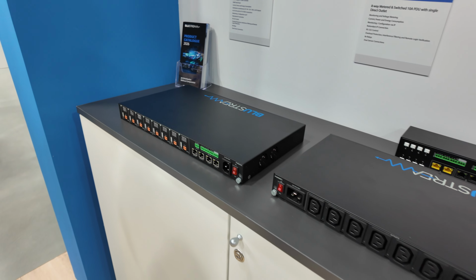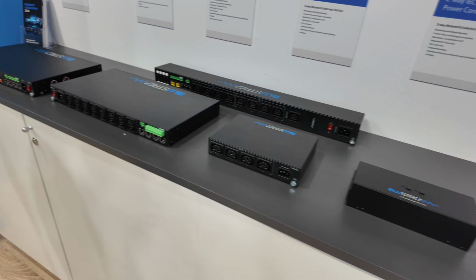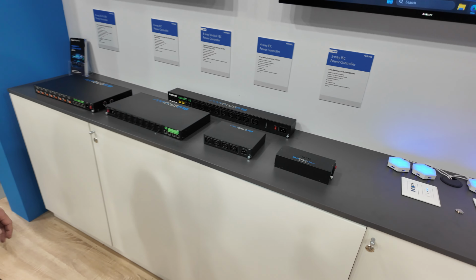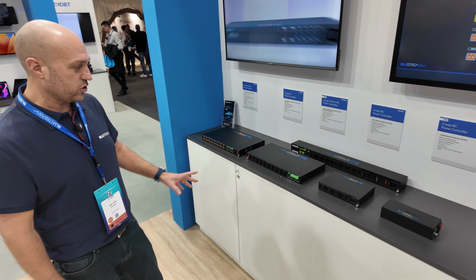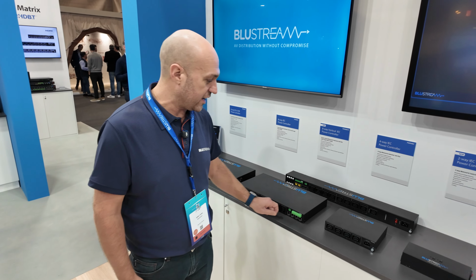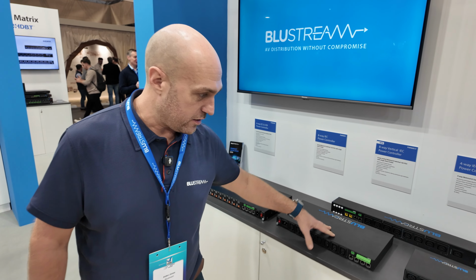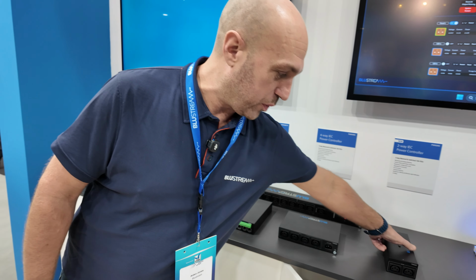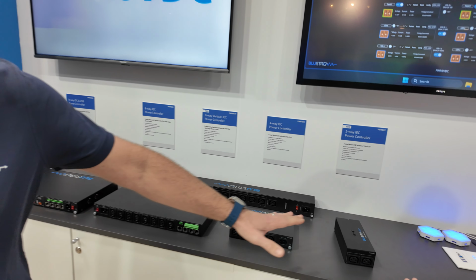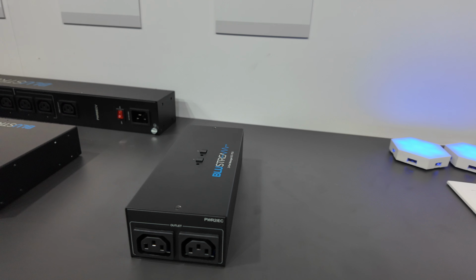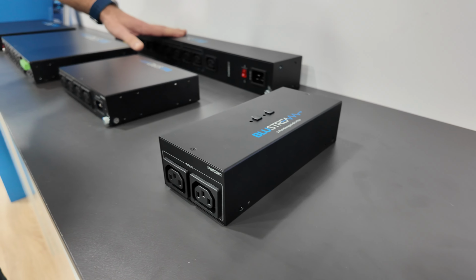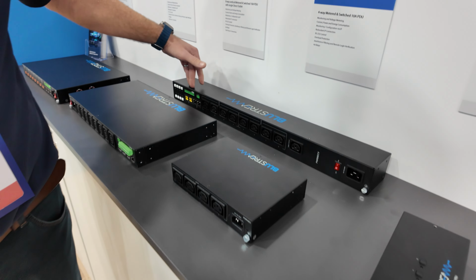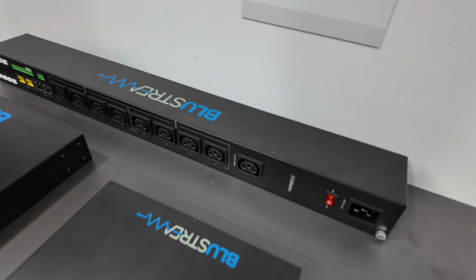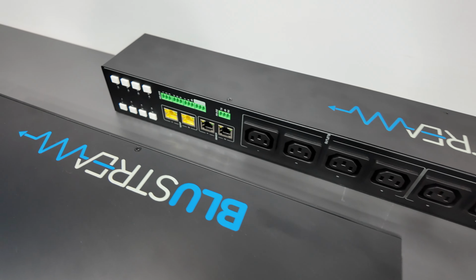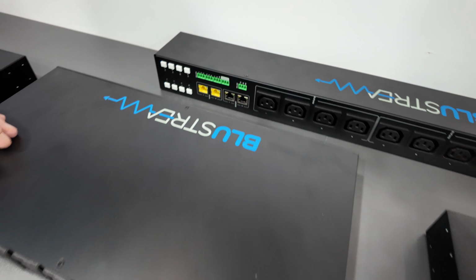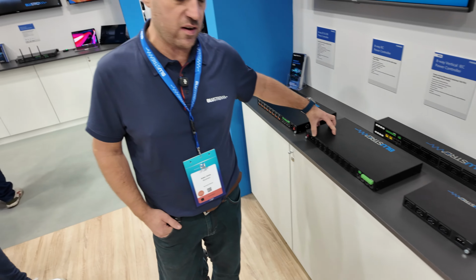So 3 products in market at the moment, with 2 more coming in the next 4 months. We'll start first with the IEC Mains PDU - there's an 8-way, a 4-way, and what will be a 2-way version coming in the next quarter. Also coming soon is the 8-way strip mount, for the back of a rack, vertically mounted - essentially the same as the 8-way rack mount horizontal variation.